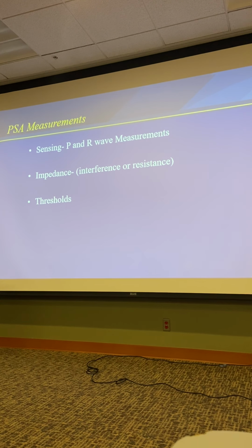In any event, very high resistance is no good because the amount of battery energy that it would take to keep working would deplete the battery very quickly. And a very low resistance or low impedance is no good because it's very unlikely that that electrical signal is actually getting to the heart. It's probably going partway down the lead to wherever the short is, and then going right back to the can and never pacing the heart. And then thresholds. When we deliver a signal, does the heart beat?